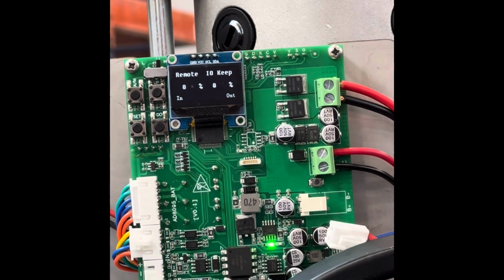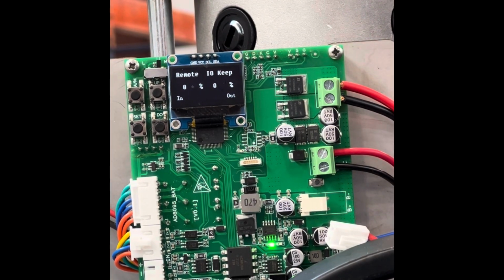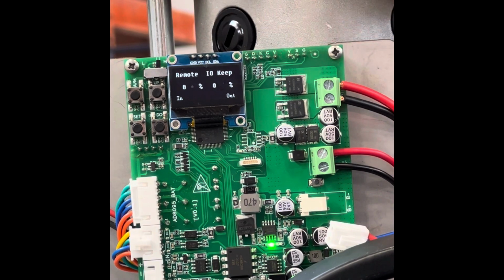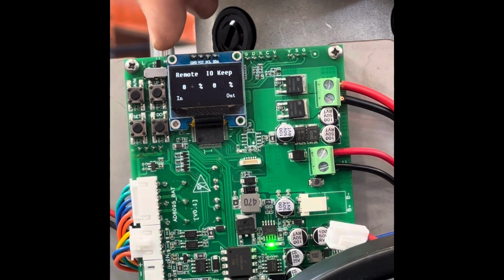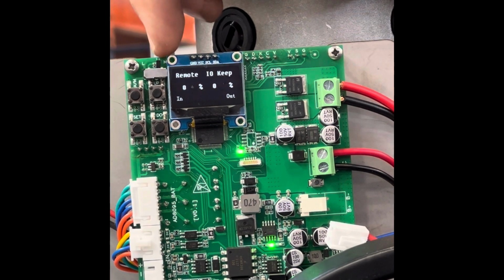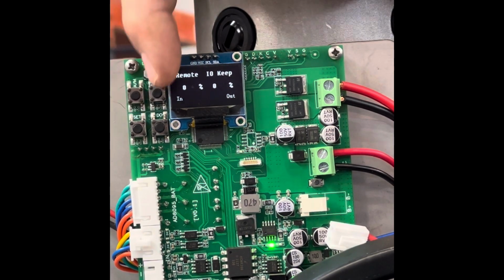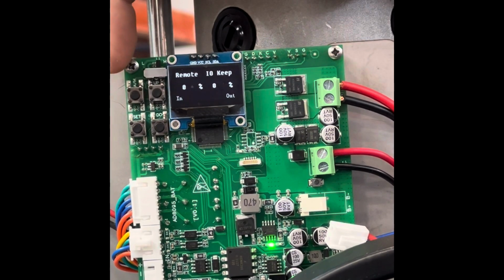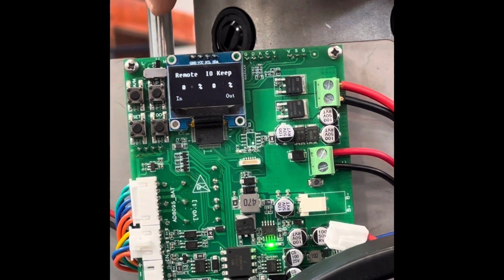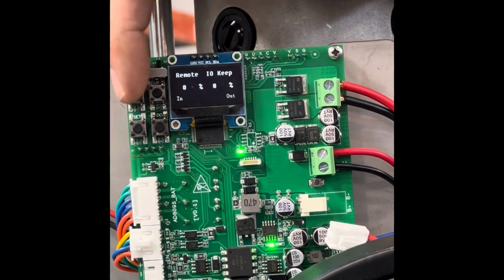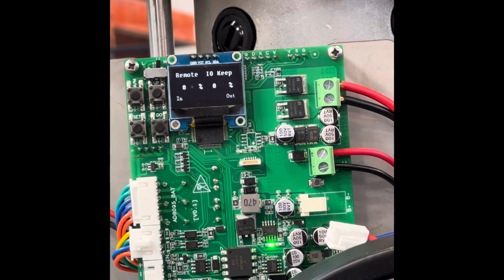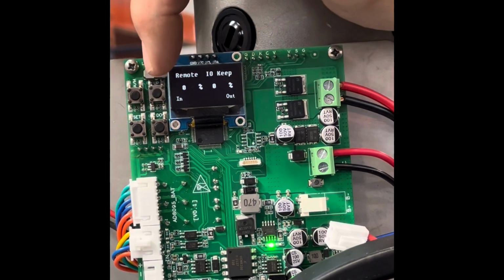Or this actuator can also do 4 to 20 milliamp modulating. So right now it's set up in the keep mode. This is a 24 volt actuator. Up here at the top, you've got a switch that says L for local and M for remote. You've got your standard 4 buttons, once you get into the menu, these are your buttons for programming and calibrating. Top left is typically your back button. The bottom left is your set or enter button. The top right is your up button, toggle up and then toggle down.